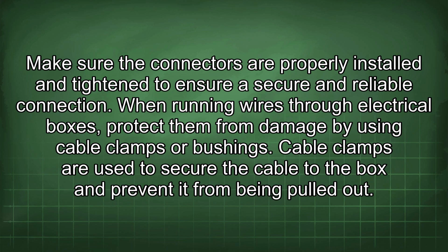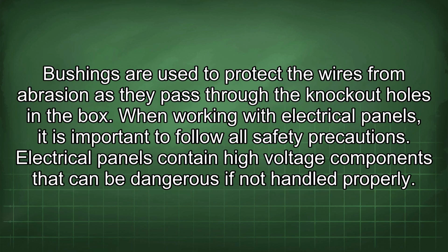When running wires through electrical boxes, protect them from damage by using cable clamps or bushings. Cable clamps are used to secure the cable to the box and prevent it from being pulled out. Bushings are used to protect the wires from abrasion as they pass through the knockout holes in the box.